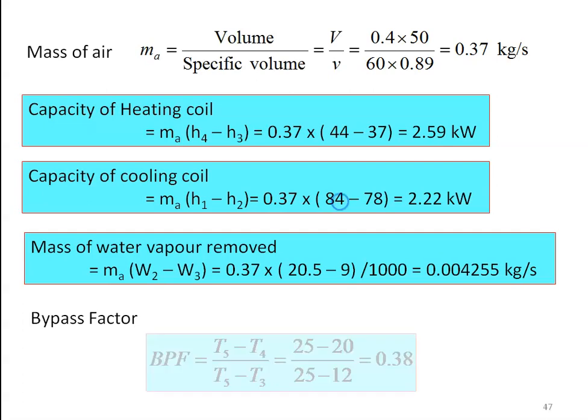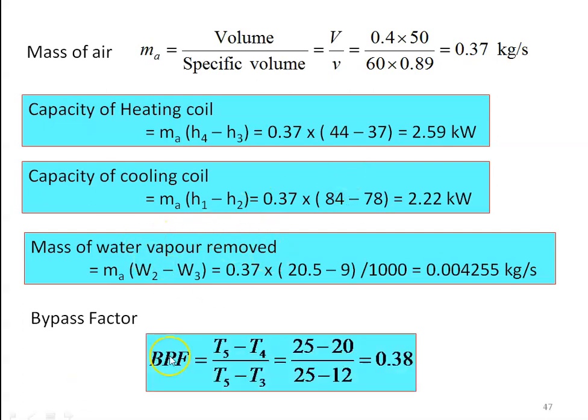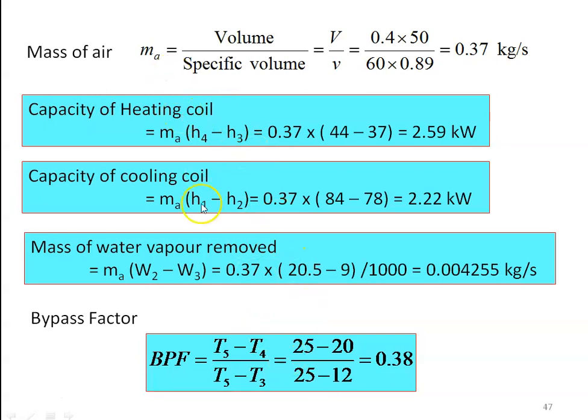For the bypass factor: in the heating process, bypass factor = (surface temperature − outlet temperature) ÷ (surface temperature − inlet temperature) = (25 − 20) ÷ (25 − 12) = 0.38. So the bypass factor of the heating coil is 0.38. These are all the answers for this problem.